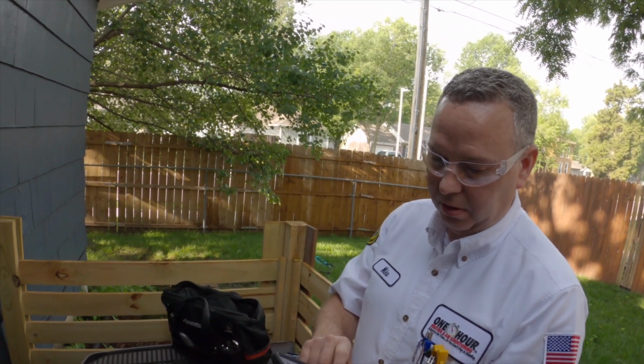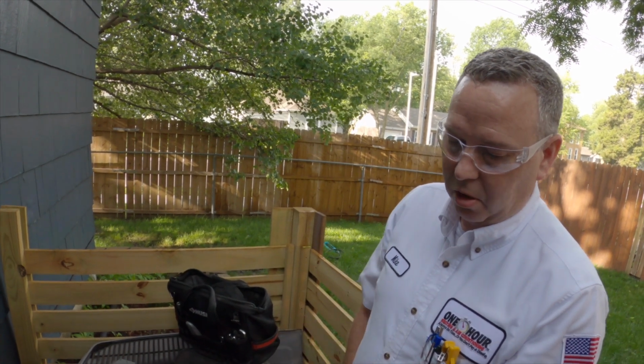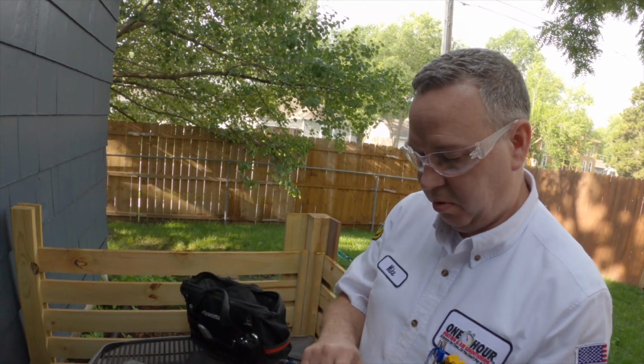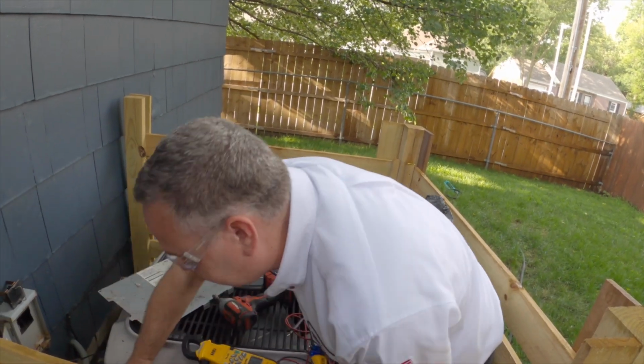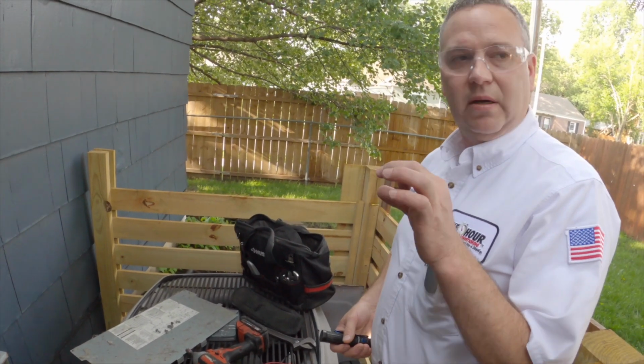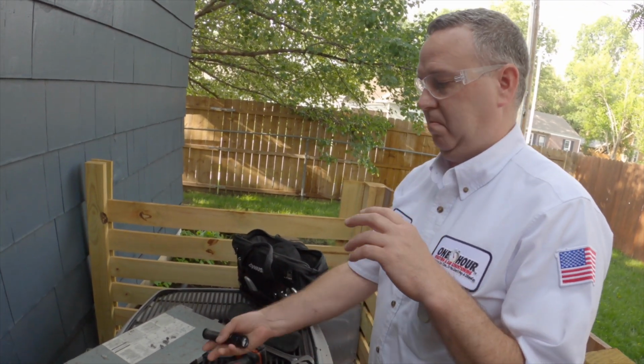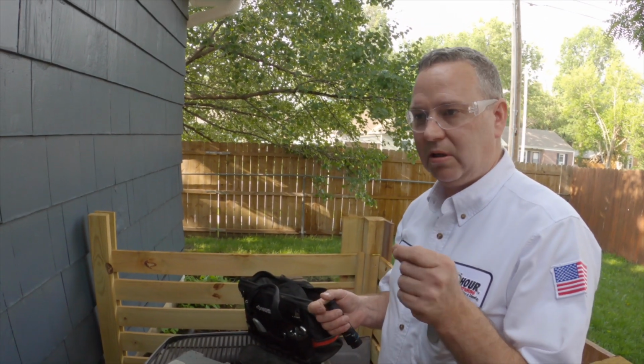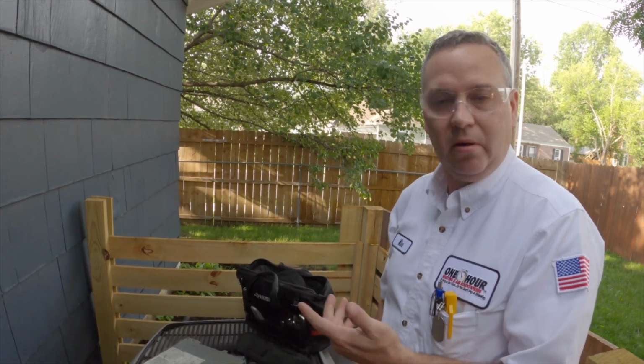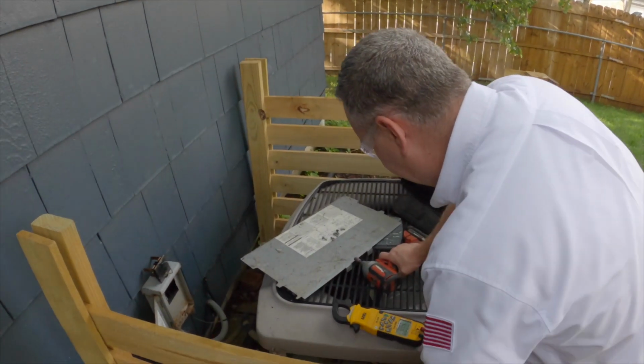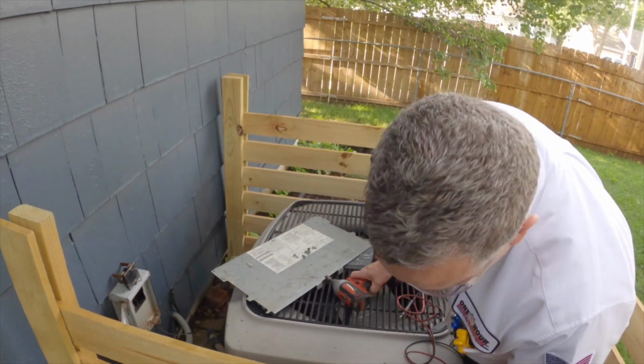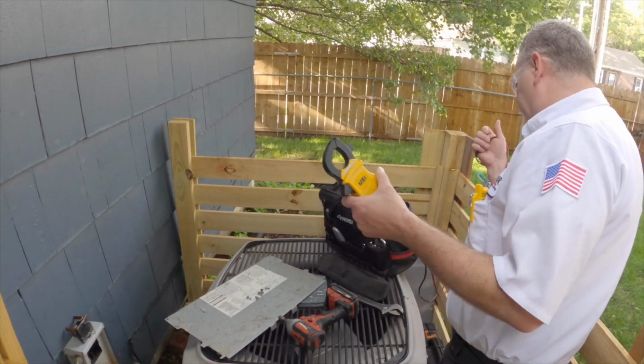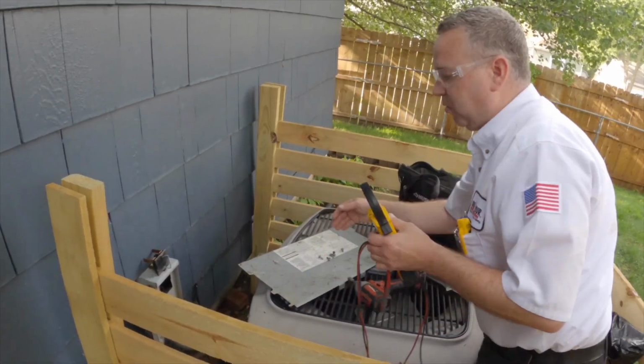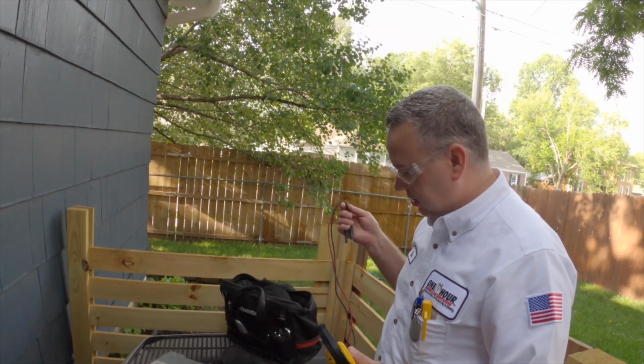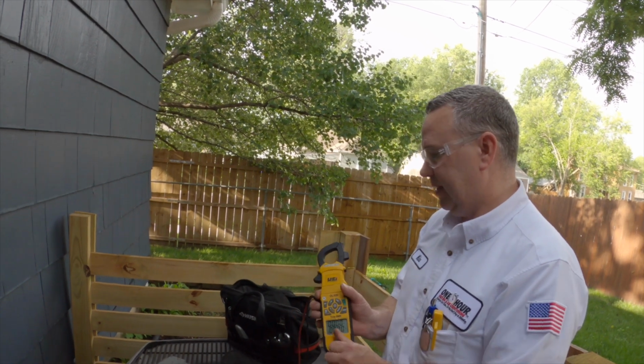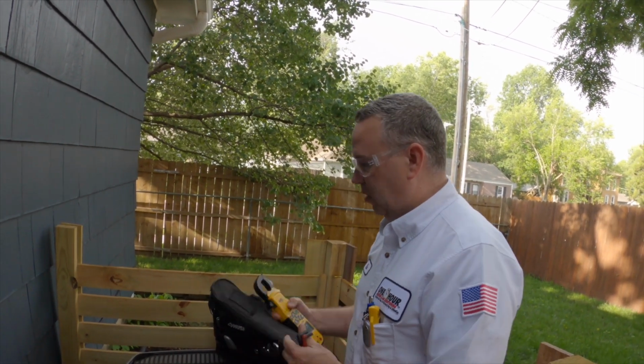You can see that it's really dark and charred and pitted, so it's definitely something to bring up to the customer. And sometimes, if it doesn't make contact like it's supposed to, it can make the system short cycle, which is a possibility as well. Other than that, it looks like it could use a little bit of maintenance. The inside of the electrical compartment hasn't been cleaned in a while. The outside coil looks like it could use some maintenance as well. I'm going to put things back together, try to start things back up and check refrigerant charge, just to let him know what's going on.